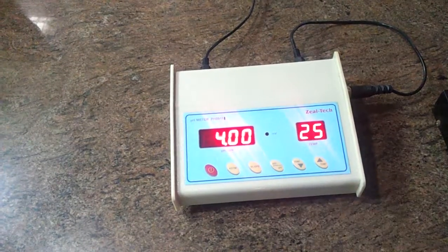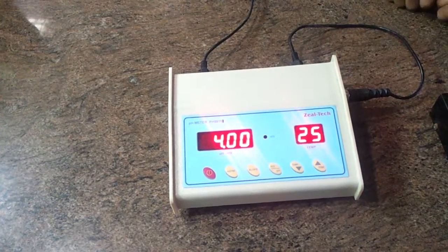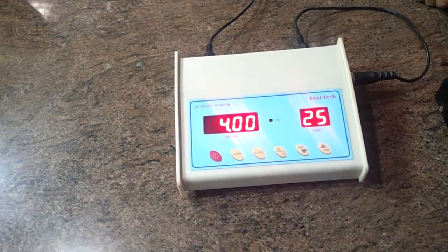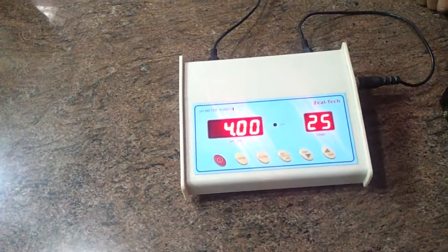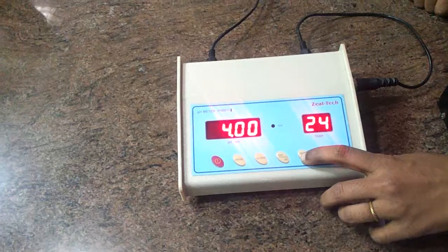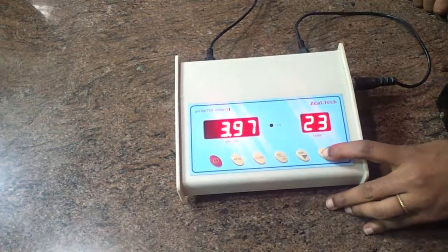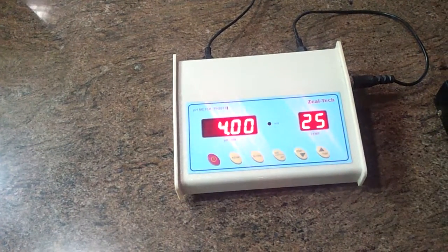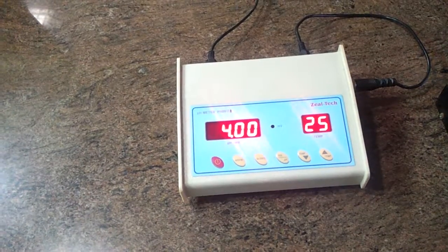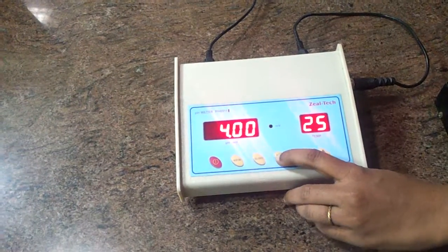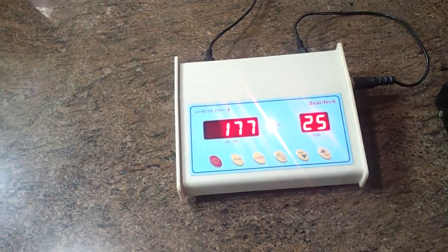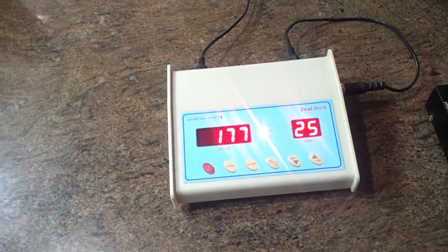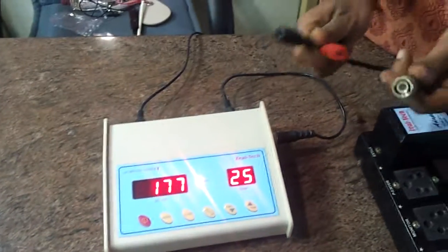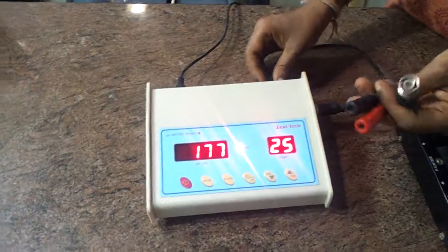Before calibration, adjust the temperature. Note the temperature of the room or solution by thermometer and select the same temperature by pressing the temperature up or down keys. To read millivolt mode, press the millivolt or pH key. The LED will glow. This instrument can be used as a potentiometer with the help of the BNC to banana socket cord by switching over to millivolt mode.